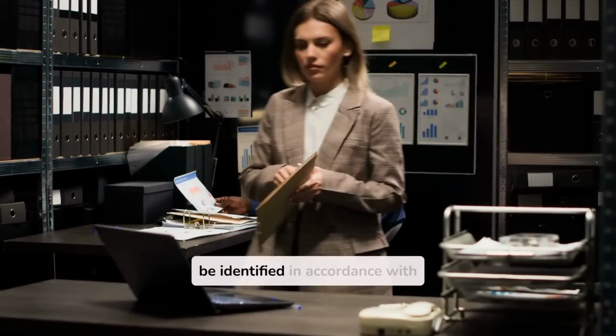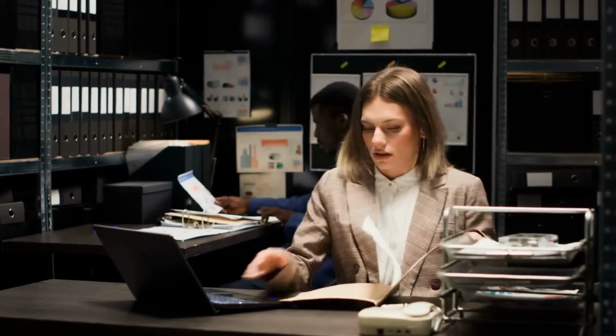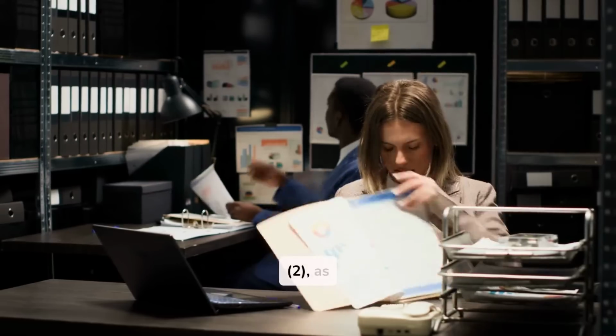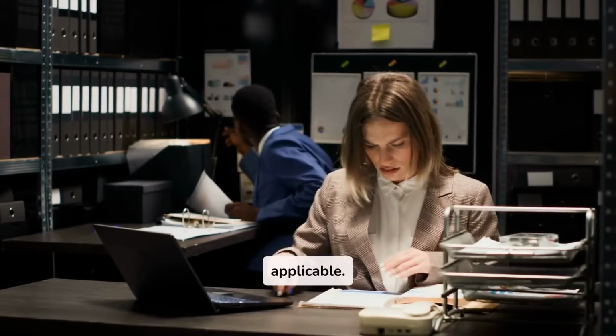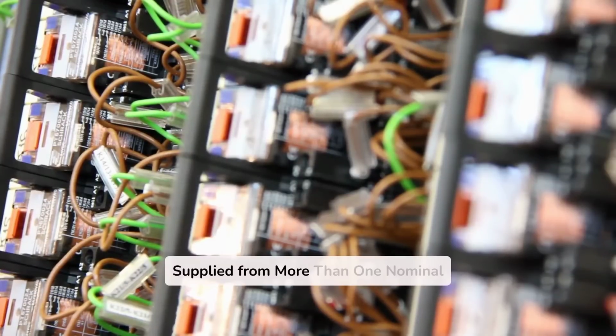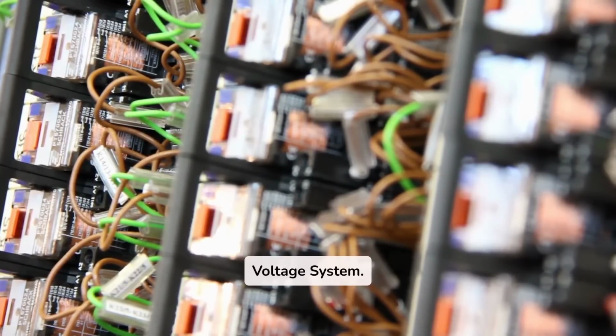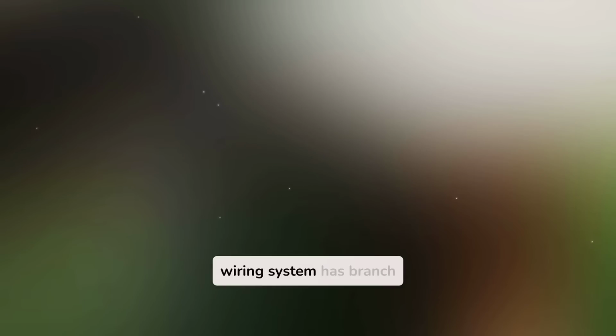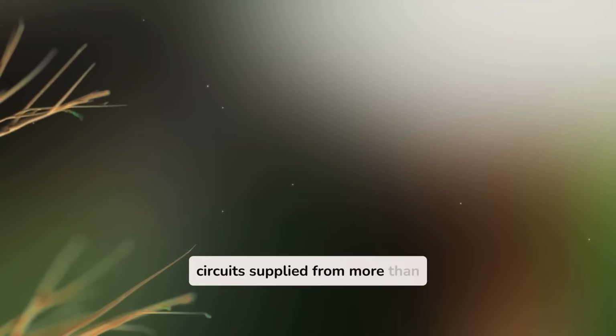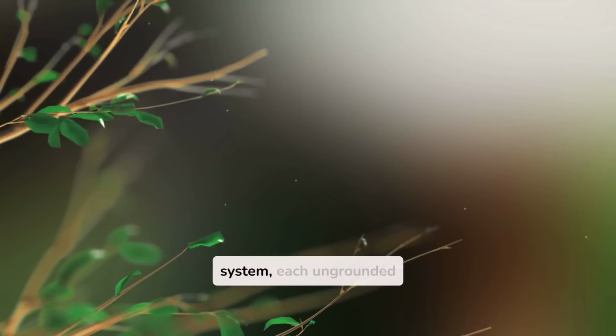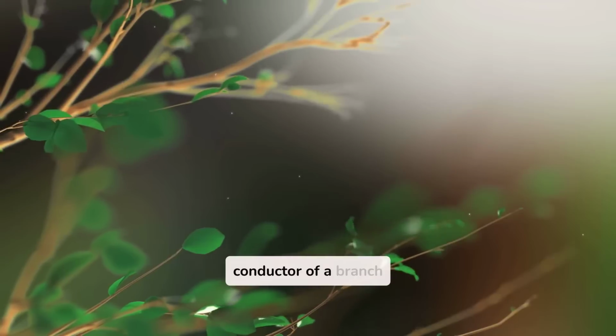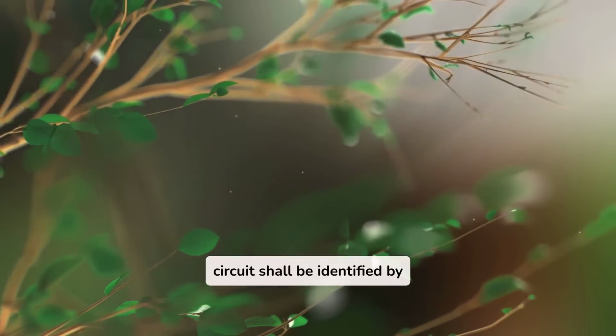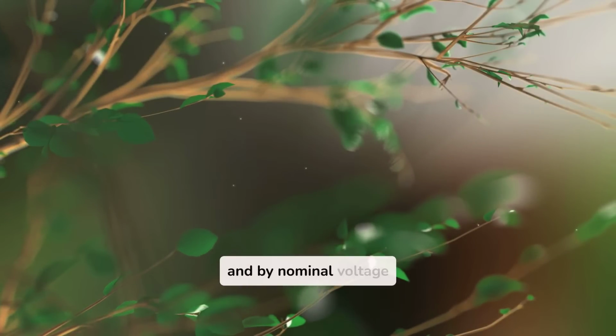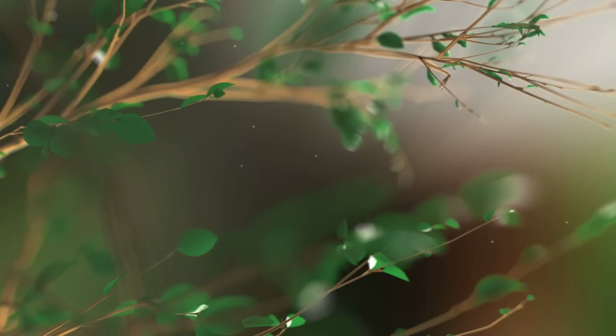Ungrounded conductors shall be identified in accordance with 210.5(C)(1) or (2), as applicable. 1. Branch circuit supplied from more than one nominal voltage system. Where the premises wiring system has branch circuits supplied from more than one nominal voltage system, each ungrounded conductor of a branch circuit shall be identified by phase or line and by nominal voltage system at all termination, connection, and splice points in accordance with 210.5(C)(1)(a) and (C)(1)(b).